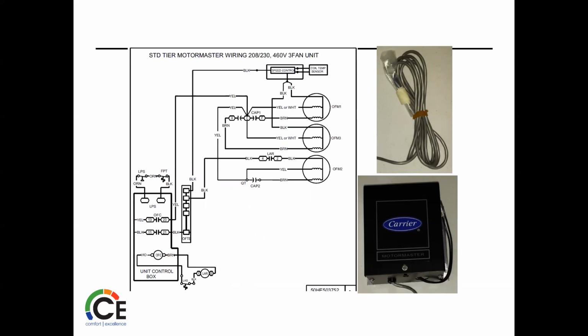All right, so we talked about this, just the basic wiring there. You can see your low pressure switch, your outdoor fan contactor, your unit control box. And now we're using the speed control and the temp sensor to send power to the motors. And then your low ambient relay to one of your other motors just to monitor what's going on. So that's a 460 3-fan unit.